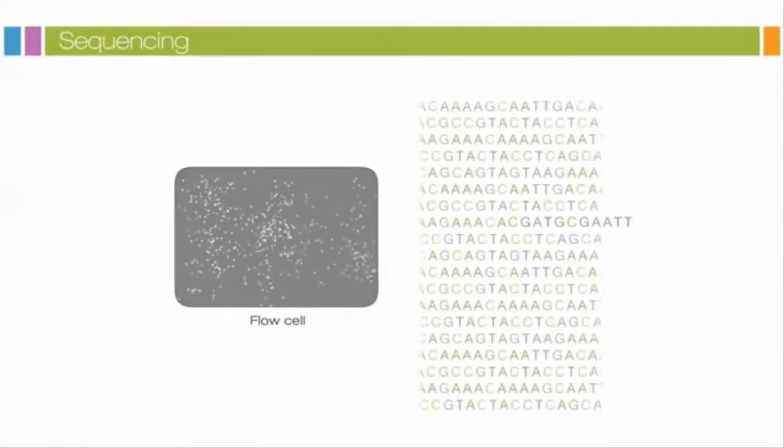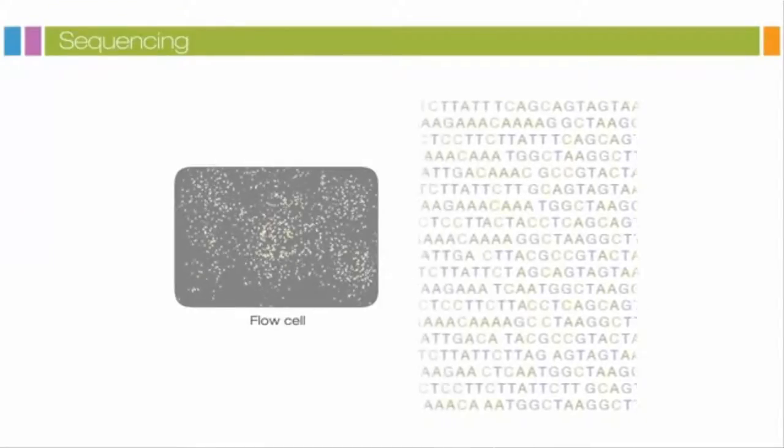Only one is incorporated based on the sequence of the template. After the addition of each nucleotide, the clusters are excited by a light source and a characteristic fluorescent signal is emitted. This proprietary process is called sequencing by synthesis. The number of cycles determines the length of the read. The emission wavelength, along with the signal intensity, determine the base call. For a given cluster, all identical strands are read simultaneously. Hundreds of millions of clusters are sequenced in a massively parallel process. This image represents a small fraction of the flow cell.